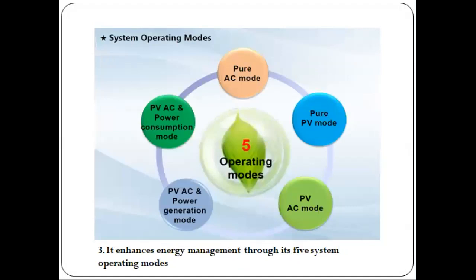Number 3, it enhances energy management through its 5 system operating modes. By utilizing PV electric current to directly drive the centrifugal chiller and by distributing power through the power generation and consumption integrated system, the utilization ratio of PV power is approximately 99%. Besides, system efficiency is increased by 6 to 8% as compared to combining a grid-connected PV system and air conditioning system. According to the operating condition of the PV system and centrifugal chiller, it can switch to 5 different working modes as regards power generation and consumption. Actually, the switch between each mode takes less than 10 milliseconds.